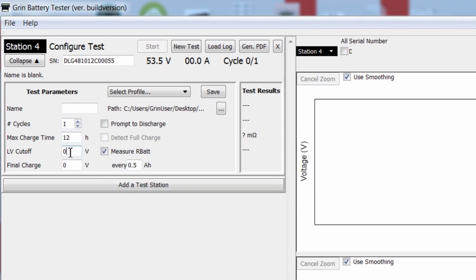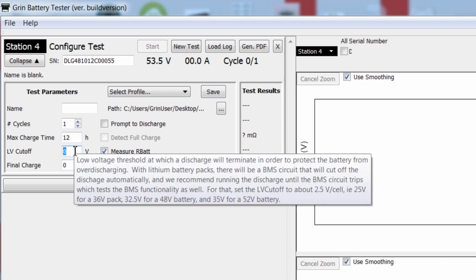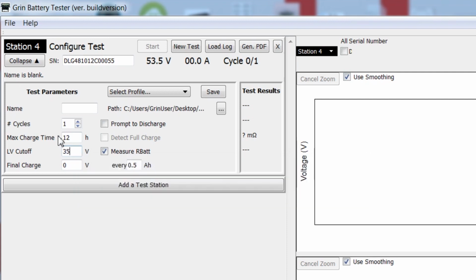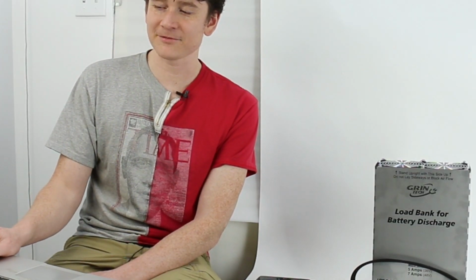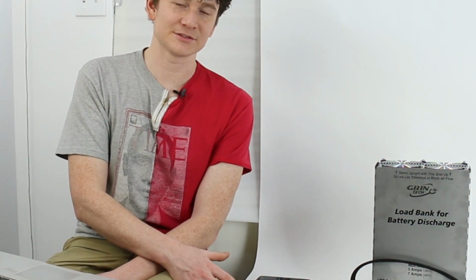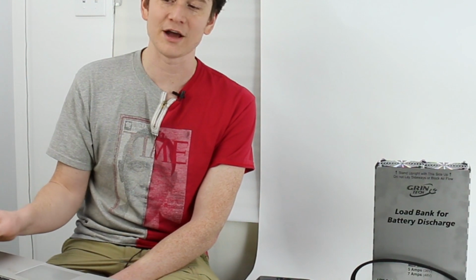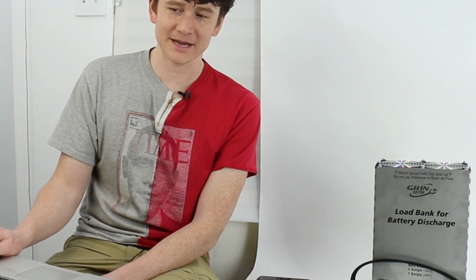There's an optional field for a low voltage cutoff. On a 48 volt battery, you'd typically discharge to about 40 volts to get it all the way flat. If you want to confirm the battery management circuit works, you could set it lower, say 35 volts, where the BMS should really shut off. If you see the discharge graph go all the way down to 35 volts, that confirms the BMS circuit isn't doing its job, which is another thing you'd want to check when assessing the health of an old random battery in the shop.